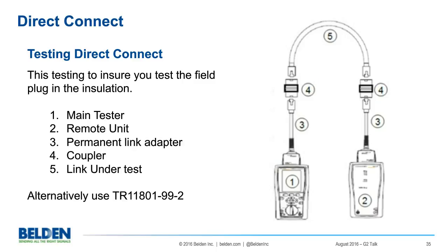That's something I hadn't really thought about before, but I think you'd be okay with a mismatch. You could have a pigtail dedicated to being part of your test, but you have to remember it becomes part of your test. So if you made a 5E pigtail and a 6A direct connect, and when you tested it to 6A performance it didn't pass, you wouldn't know if it was because of the plug you attached or because of your pigtail. Also consider that if your direct attach assembly is shielded, you'd want shield continuity, meaning your pigtail would have to be shielded as well so you could do the shield continuity test on field testers.